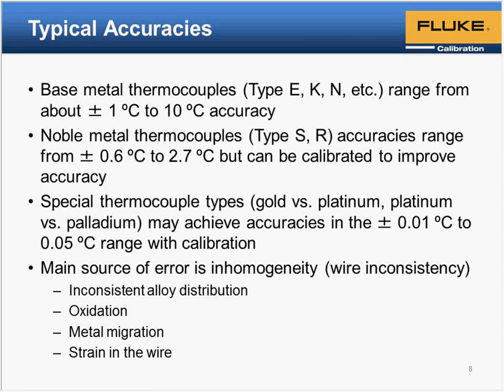And then there are thermocouples such as gold versus platinum and platinum versus palladium, which can be very, very accurate, comparable with a PRT or maybe even a high temperature SPRT, in the 0.01 degrees C to 0.05 degrees C range up to 1,000. The problem with gold versus platinum is that gold melts just over 1,000 degrees. So you have to be careful: if you go over 1,000, you'll start to approach the gold melt point, and that will ruin your thermocouple.